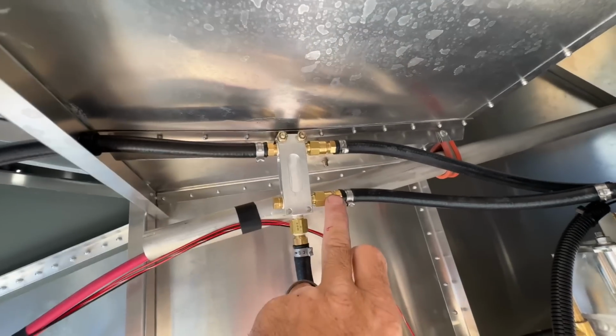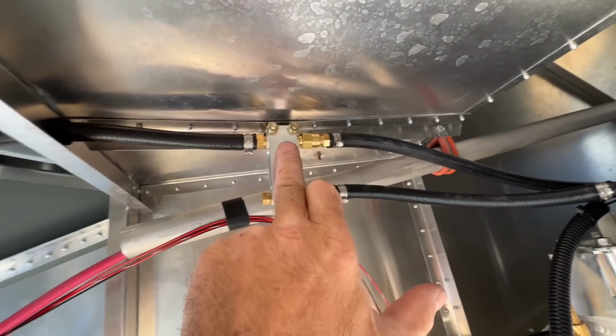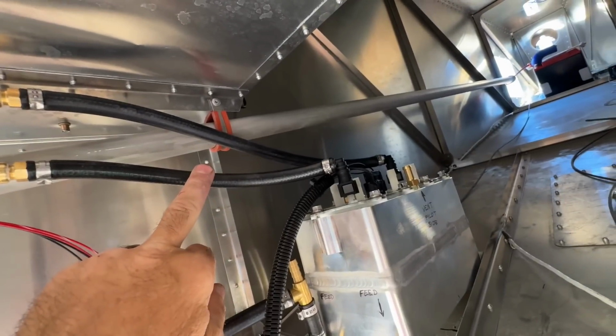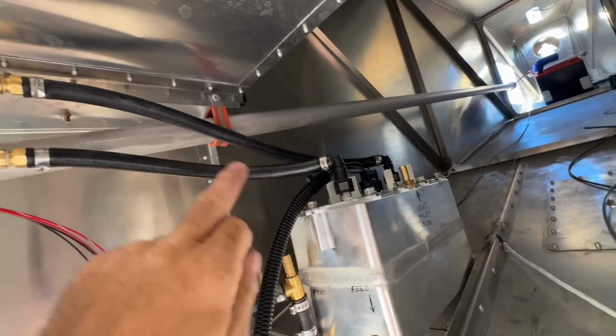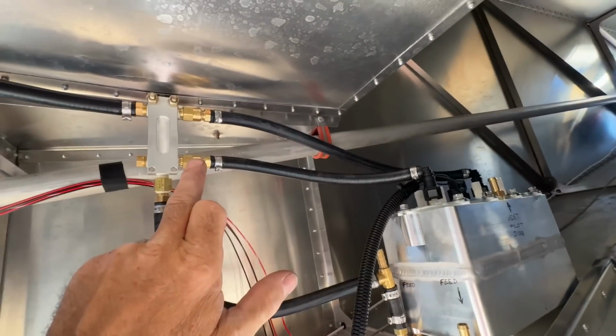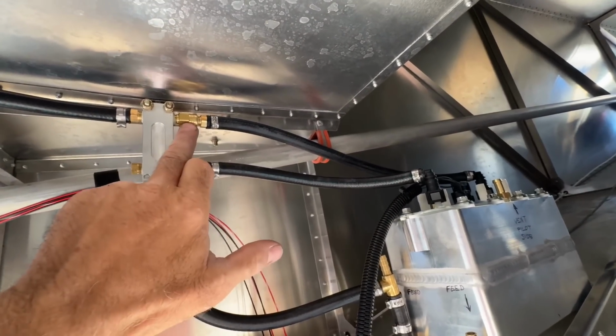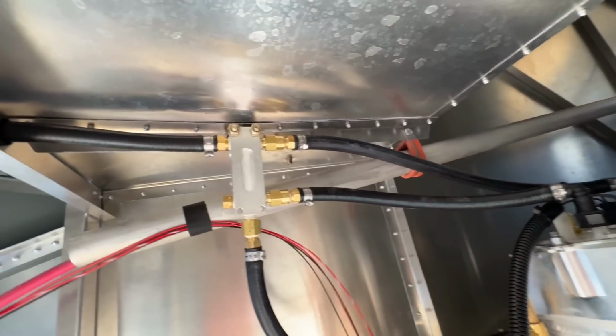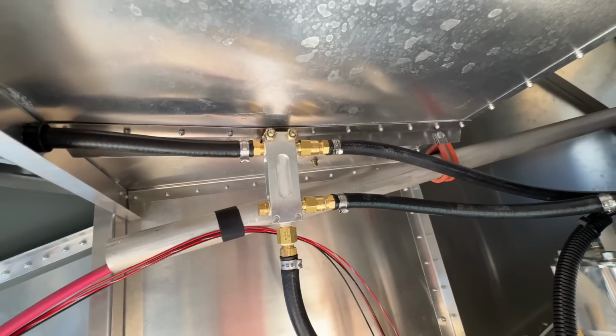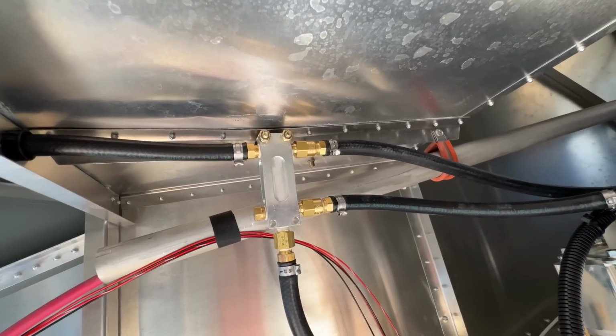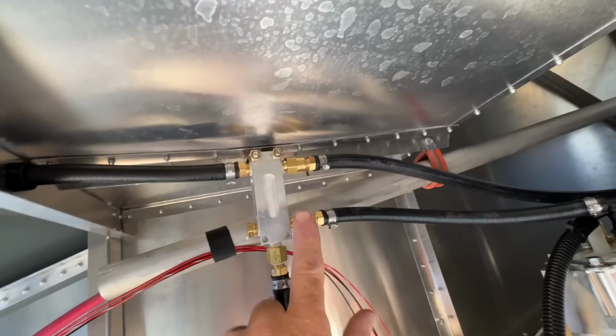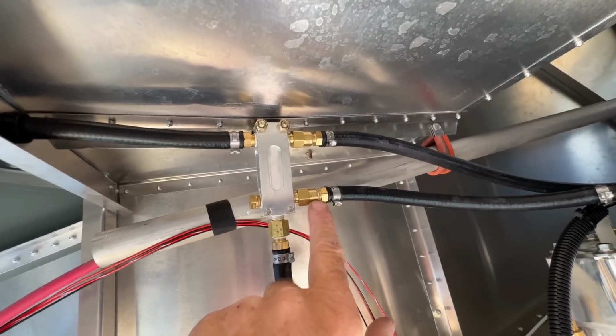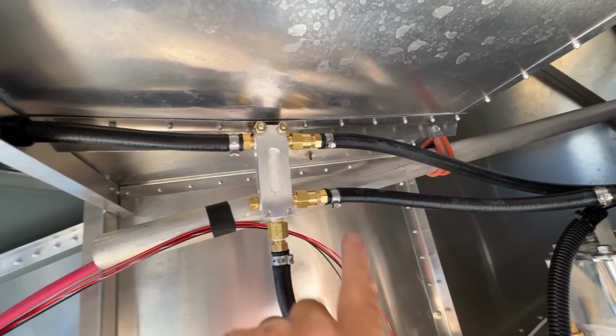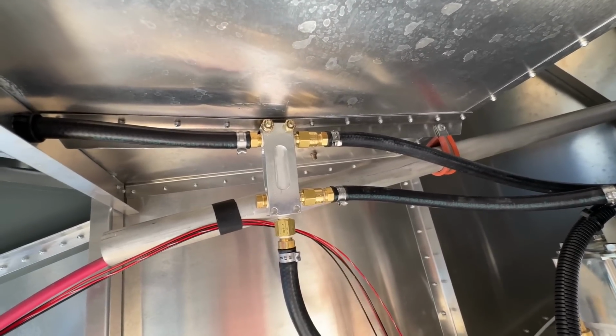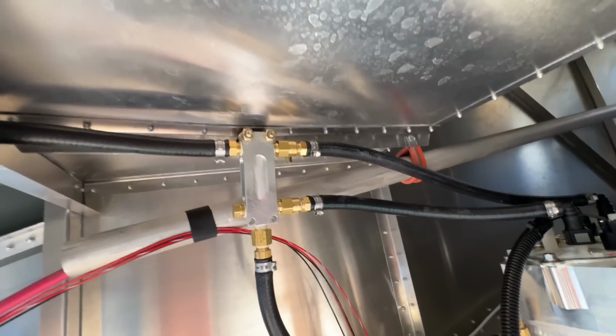Here we have a one-way check valve this way and this way, so it can't backfeed into the other pump. There are already check valves in the pumps, but we back those up with these brass check valves. If you ever have a strange scenario where you can't build pressure during initial startup, just verify these are okay—take them apart, look inside, there should be a little snap in there. Once they're working, they're working. Never had a problem with that.